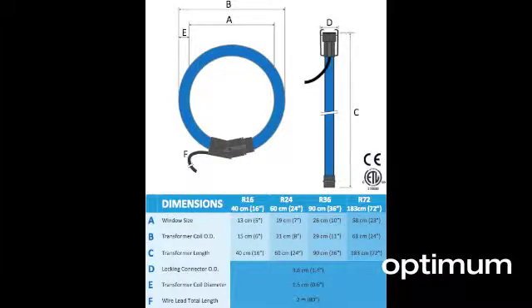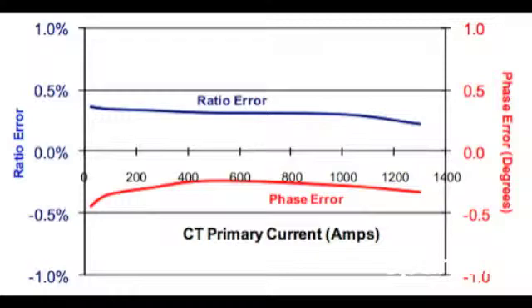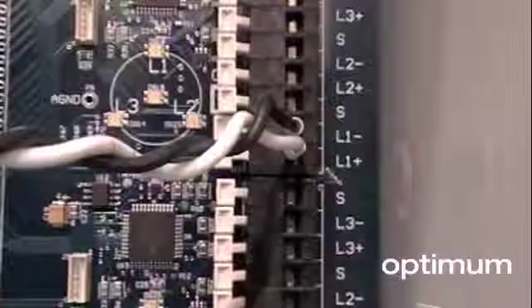Rogowski coil flexible CTs are available from 16 to 72 inches in length and measure up to 3500 amps AC. They offer tremendous accuracy throughout their range. CTs on the PowerScout can be changed later if your project needs change.